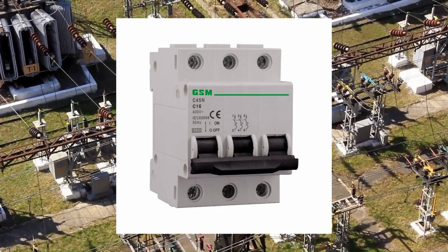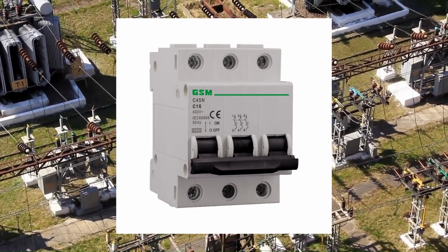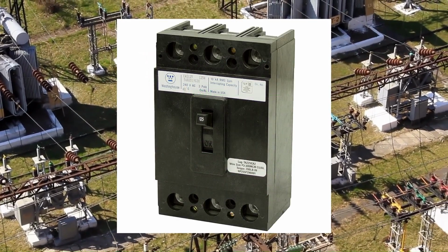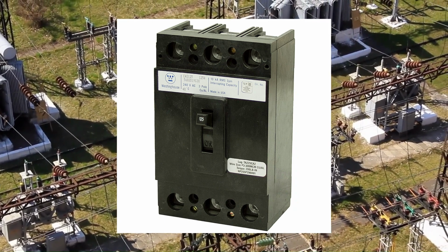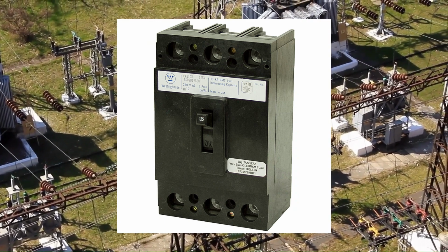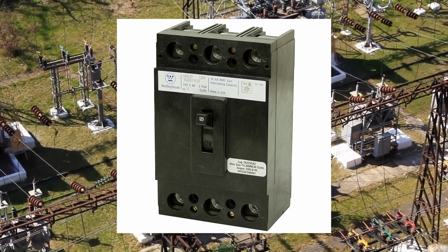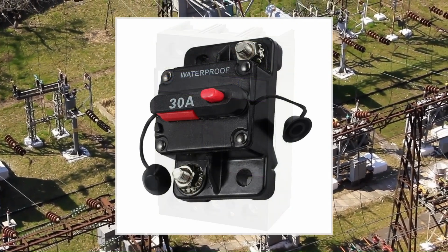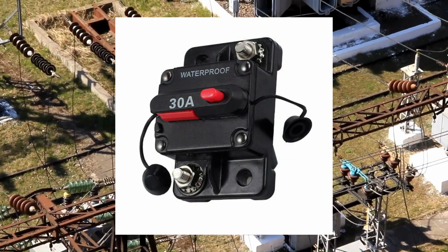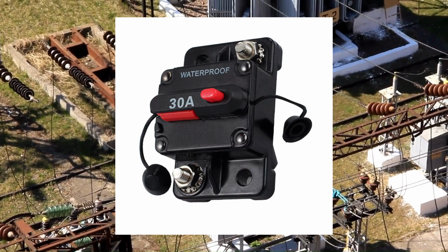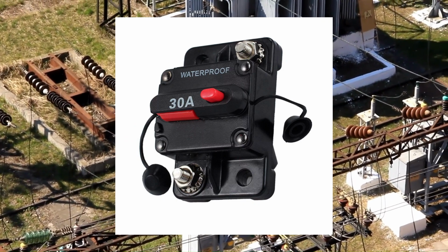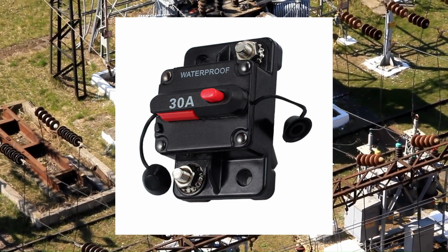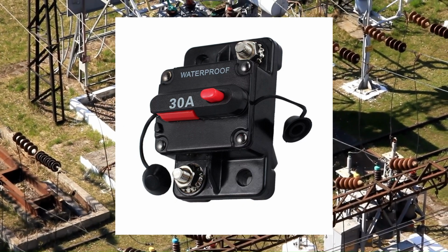The time it takes for a protective device to operate under fault current or overload conditions is referred to as the device's time current characteristics or response time. Depending on the quantity of the overload current, fast-acting rated protection devices may react to an overload in a fraction of a second, whereas normal versions may take 1 to 30 seconds. Fast-acting fuses are used to safeguard extremely delicate electronic circuits that have a constant flow of current because they are very sensitive to increased current.